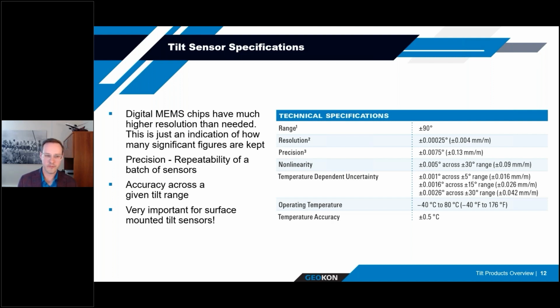So moving on to precision value, this is really the repeatability of a number of sensors. So this is typically given with a confidence interval, perhaps 99% confidence interval, and the test to come up with this value would need to be done across many sensors, perhaps 100 or a couple of hundred sensors. The next one is nonlinearity, and this really talks about the error associated with the calibrated range. So here we're talking about a nonlinearity across a plus minus 30 degree range.